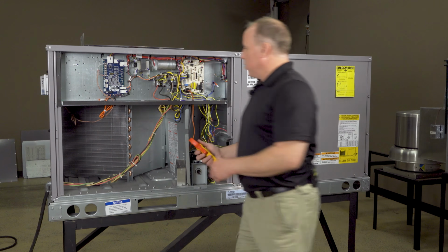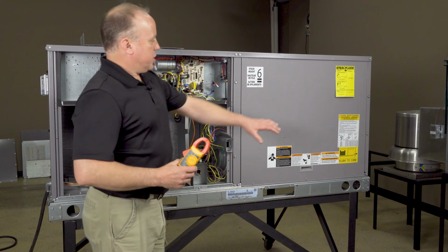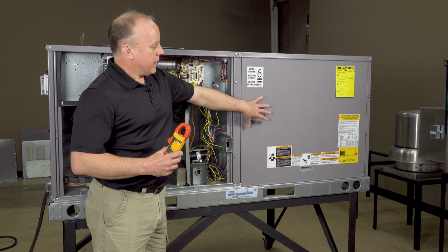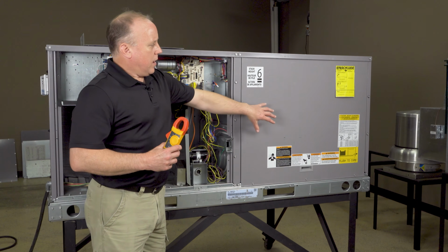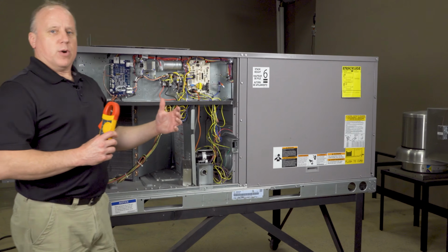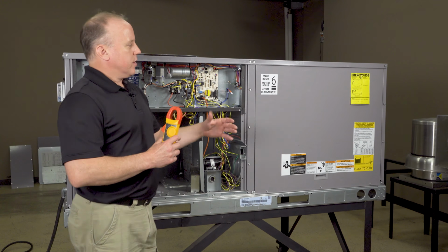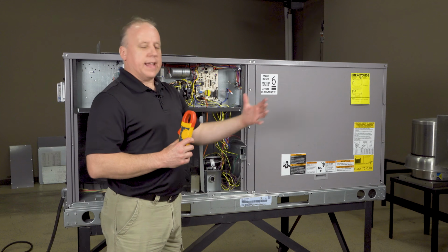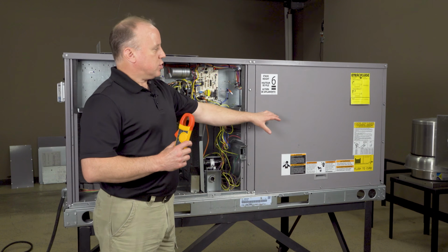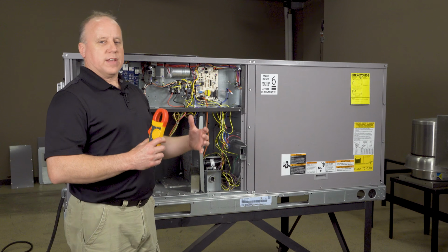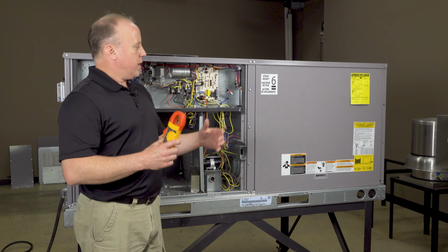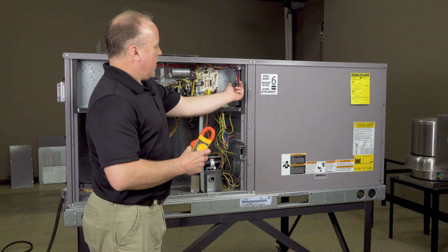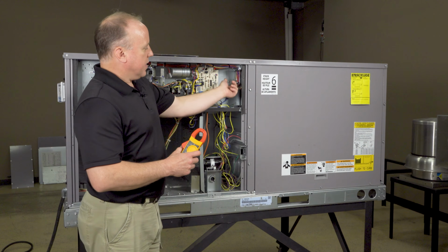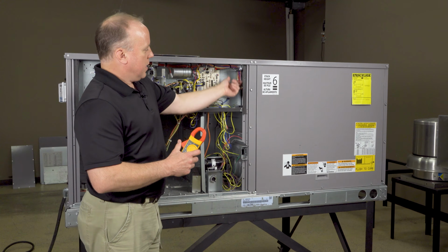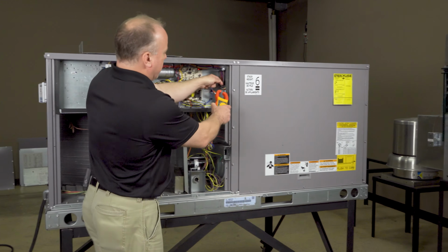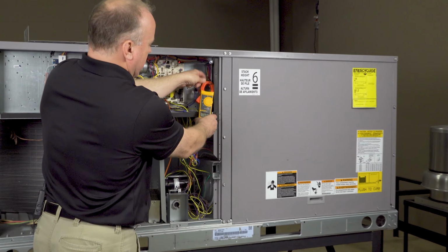And our last one we'll go to our indoor blower, which is going to be behind this door. We always want to keep that door on. That's going to give us the most accurate reading because of our static pressure, which is going to change if we take that door off. So we want to keep this door on, attached to our ductwork, everything sealed up, as close to normal operation as possible. Again, our wires are coming through. I've already isolated the wires for the motor. So I'm going to grab the black. I'm going to clamp onto that. Again, just the one single wire.